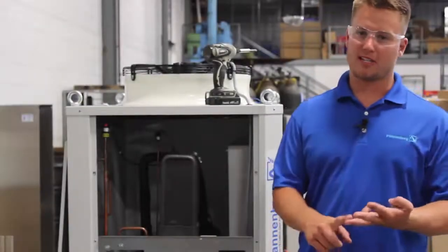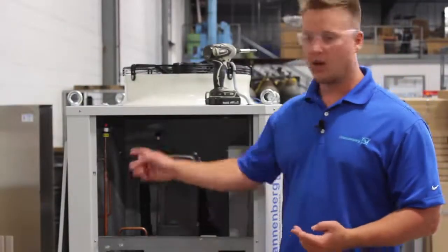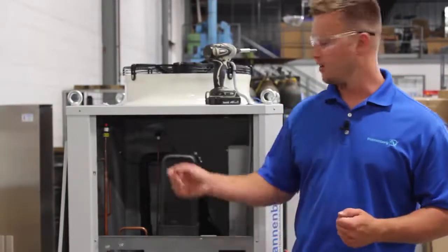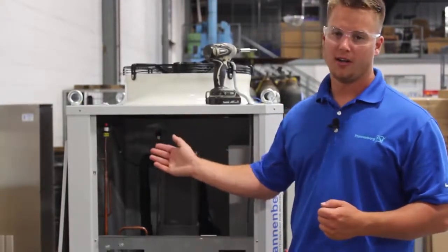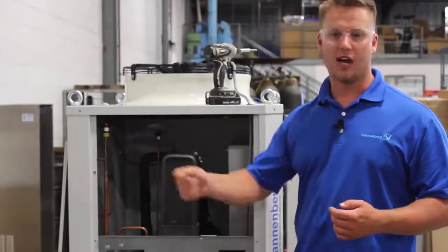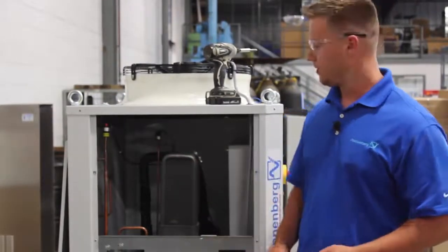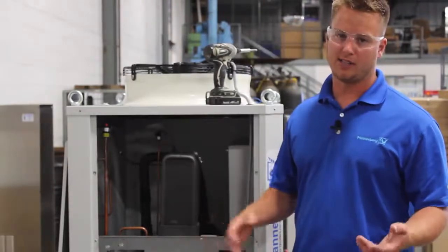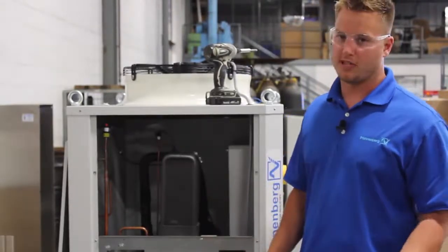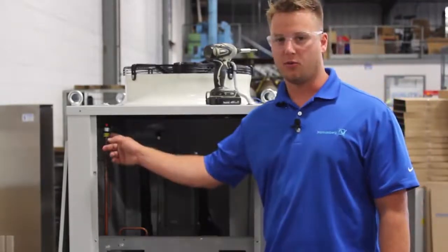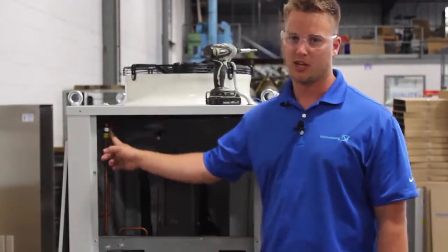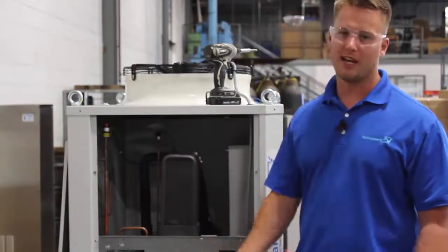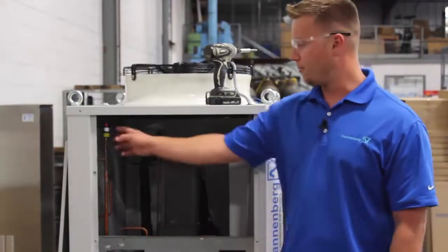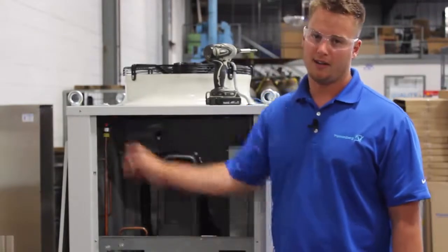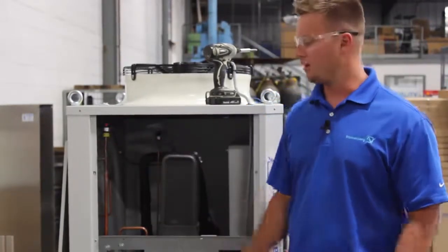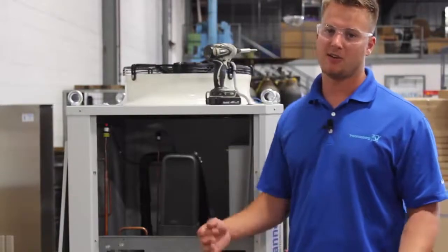Now I want to talk about protecting our compressor. Earlier we talked about a little bit of maintenance on the condenser coil. The condenser coil, after you hose it out with either water or compressed air, if the unit goes out on high pressure because it's too dirty, it's okay because we protect our compressor. This unit comes standard with a manual reset high pressure switch. This means that in order to reset it and get the chiller back up and running, you have to manually push down the reset button. This should only happen if the condenser coil gets dirty and it's in there to protect the chiller.